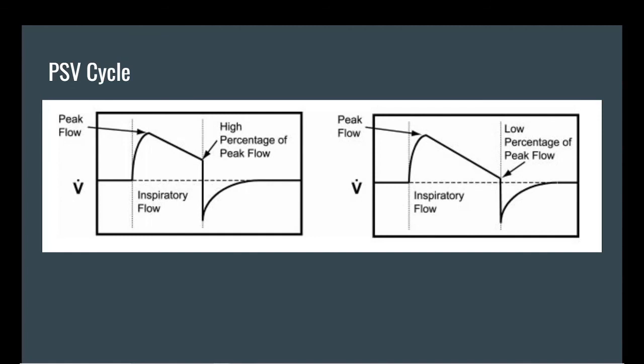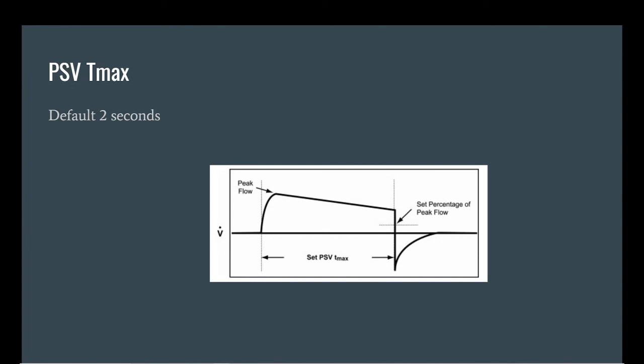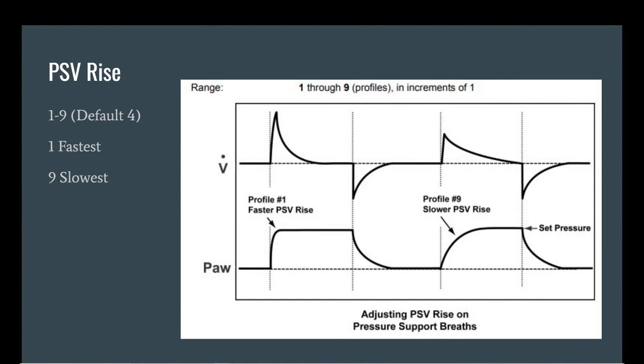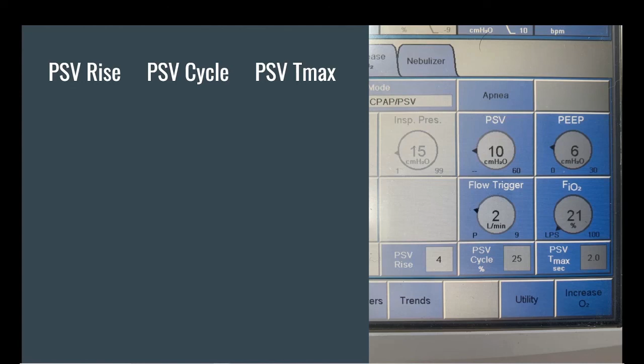PSV T-Max: if you've ever been on a BiPAP call where the patient takes a breath and then it clicks, takes another breath immediately, that's because the patient wanted to breathe for longer than the PSV T-Max. This is how many seconds it's going to allow you to automatically breathe in before it times out. That could come in handy when you have a very young patient, or if you want a very short amount of time, or if your patient just wants longer breaths and keeps having this triggered. It's good to know how to adjust that.